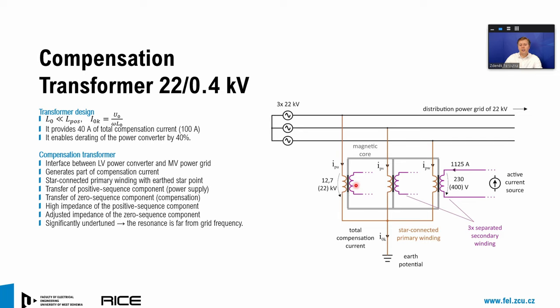The transformer is a three-phase transformer with a star connected primary winding whose neutral point is grounded, and we are operating three independent, separated secondary windings where our converters are connected. We came with a special design of the transformer which makes it possible to optimize the zero sequence impedance of the transformer, by which we are able, without any intervention of the converter, to compensate part of the fault current. In this prototype, we designed the transformer in such a way that it is able to offer 40 amps of the total compensation current of 100 amps.